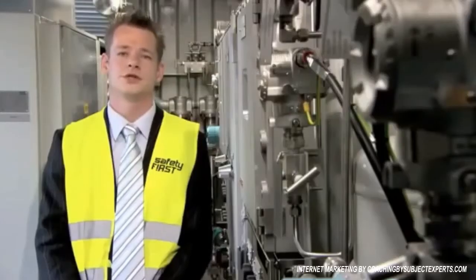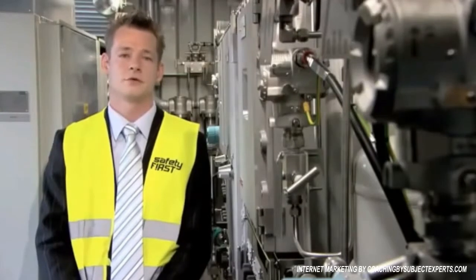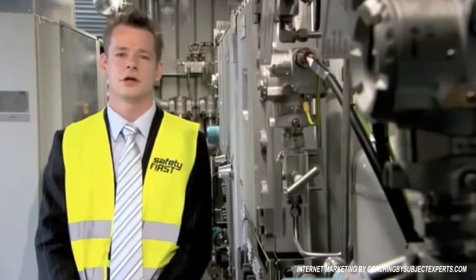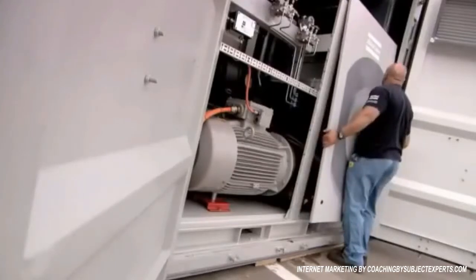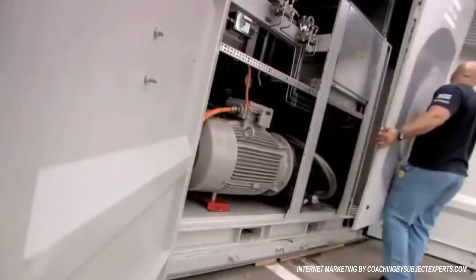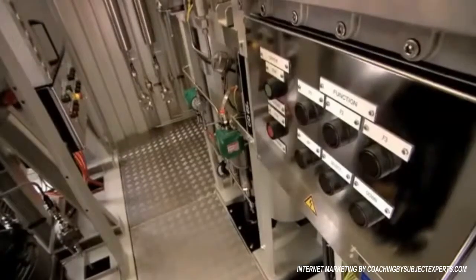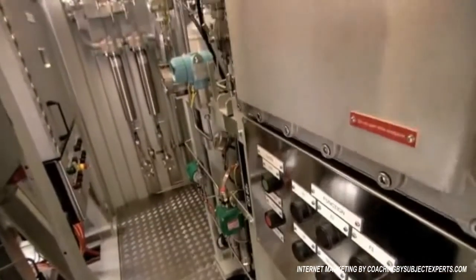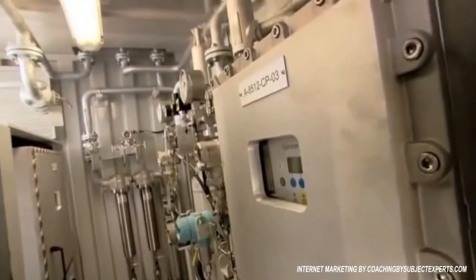The power distribution and the wiring is integrated in the base frame of the container for safety and accessibility of other equipment. The compressors will operate in a lead-lag configuration where there is a selector switch to determine the lead compressor on the power distribution panel. Should the lead compressor fail, the electronic control panel is set up automatically to switch the lag compressor to lead.